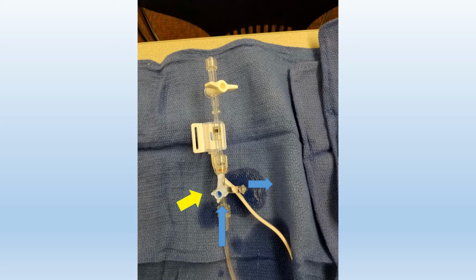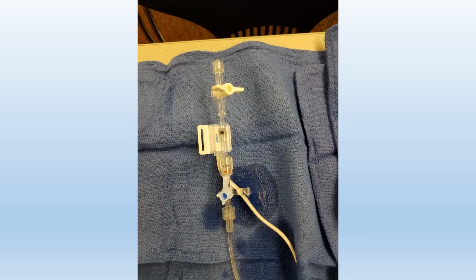So what happens is it'll limit the air going through the transducer as we flush. We want to get as much air out as possible through the bottom stopcock right there. Once we do that, we'll turn the stopcock up.